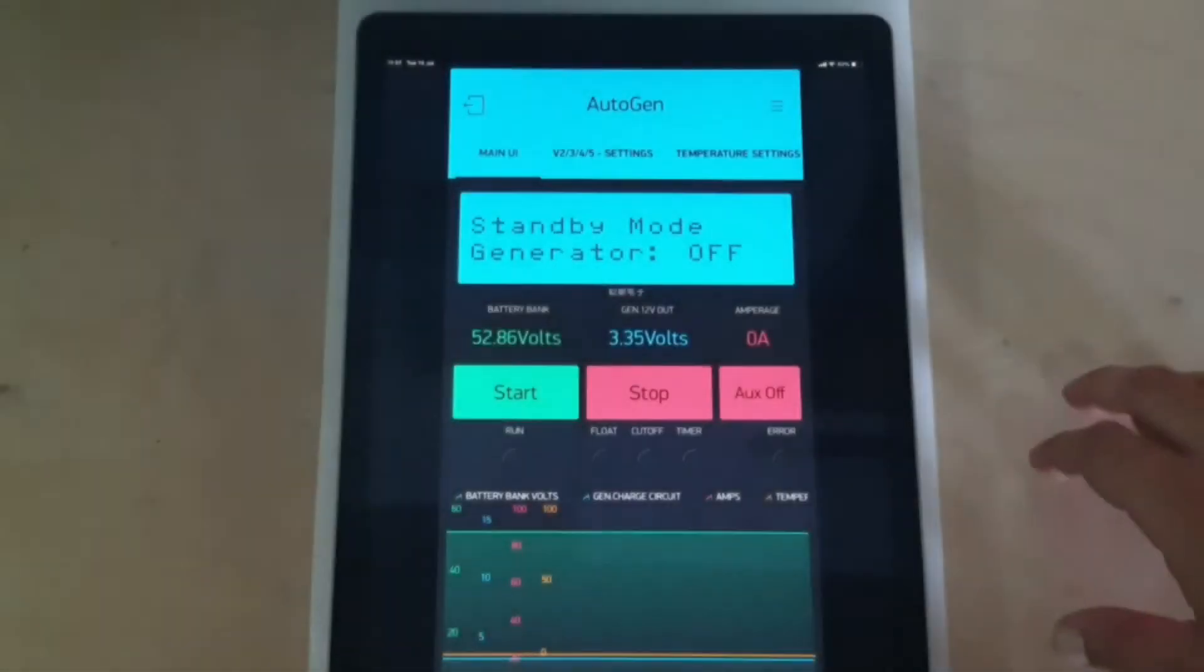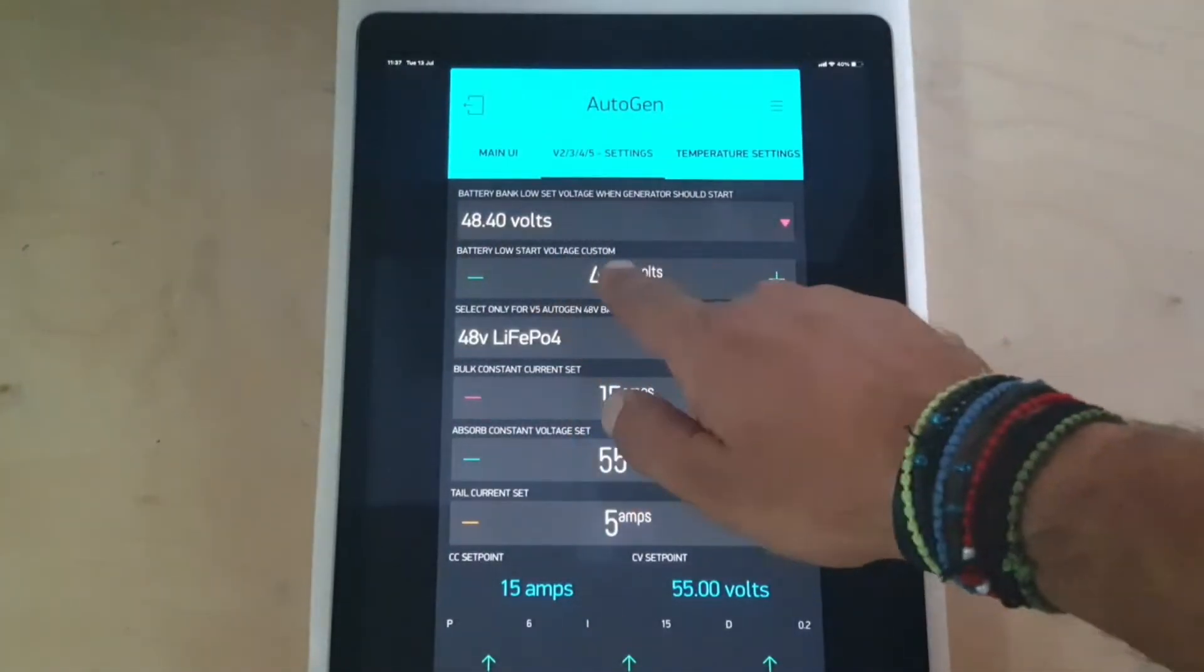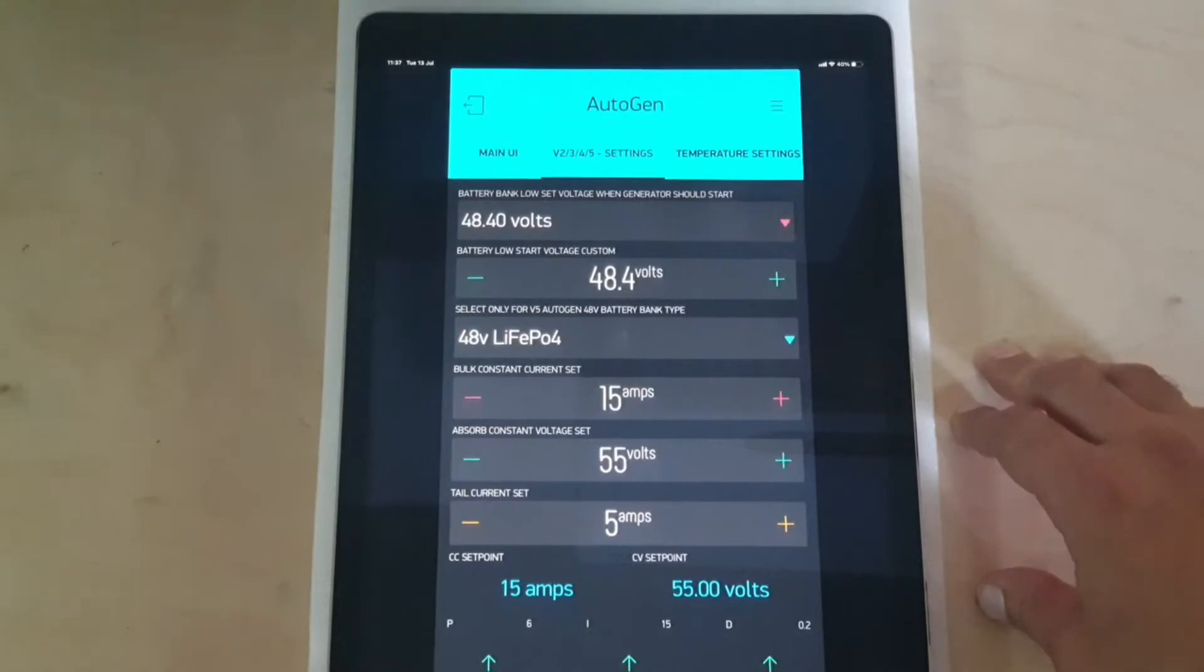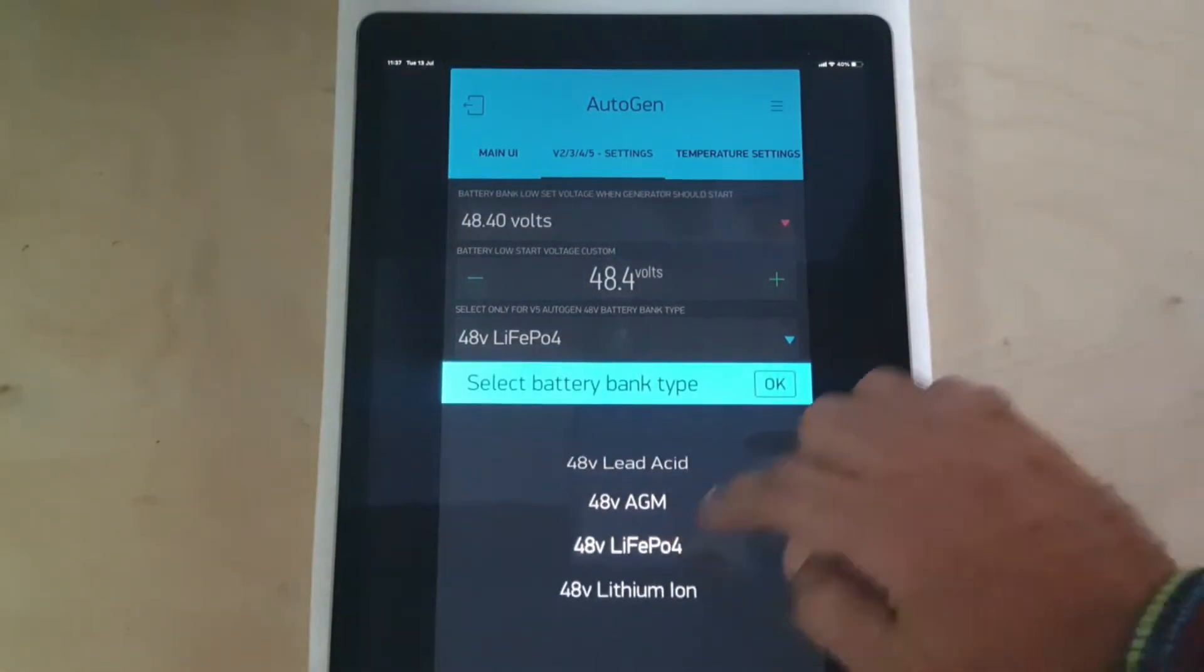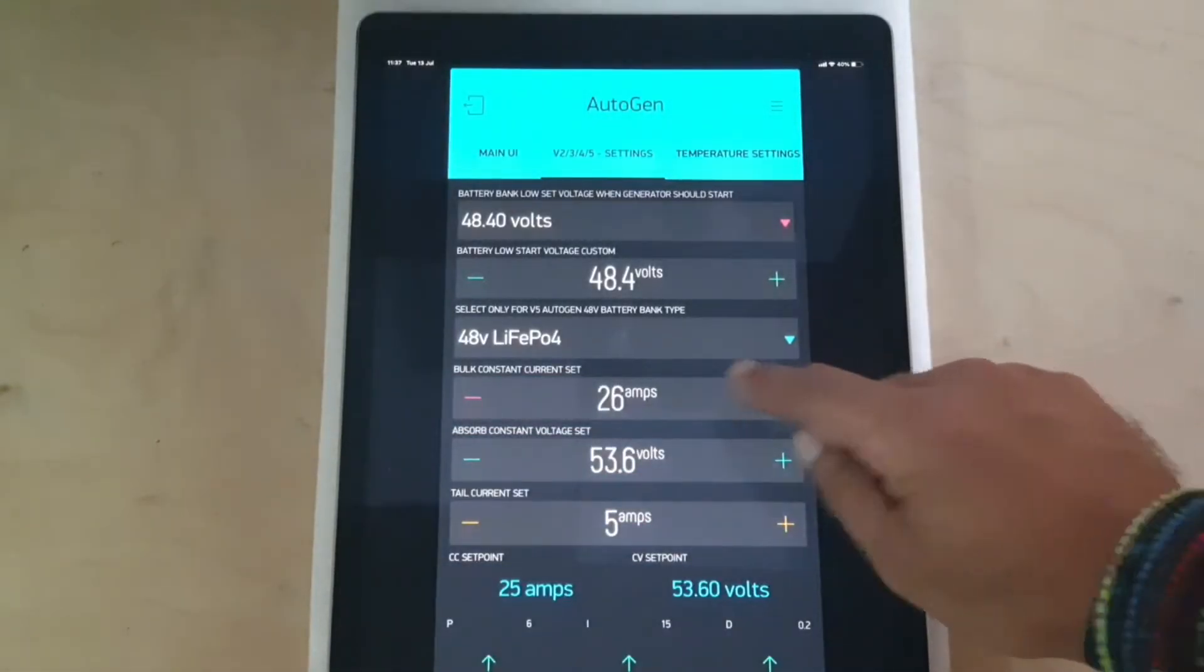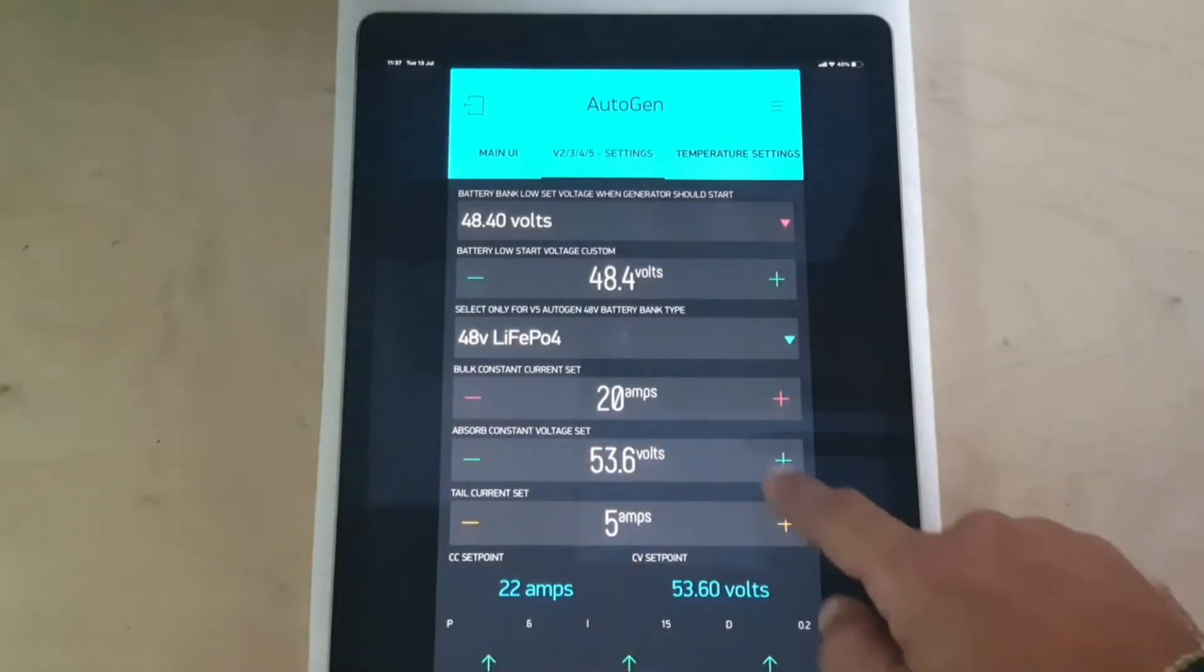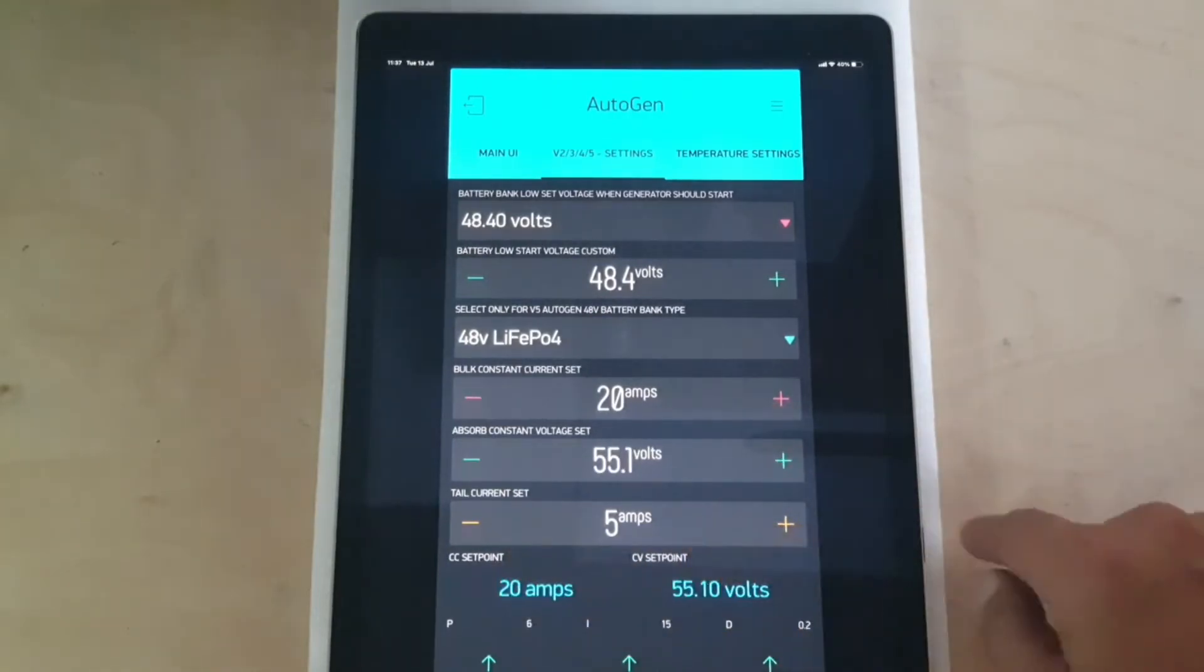A few settings before its operation. Here you can select the low battery start voltage. Select the current that you'd like to charge your battery bank with. We also have a few pre-selects depending on your battery chemistry. So we can increase, decrease current, see your absorb voltage and your tail current.